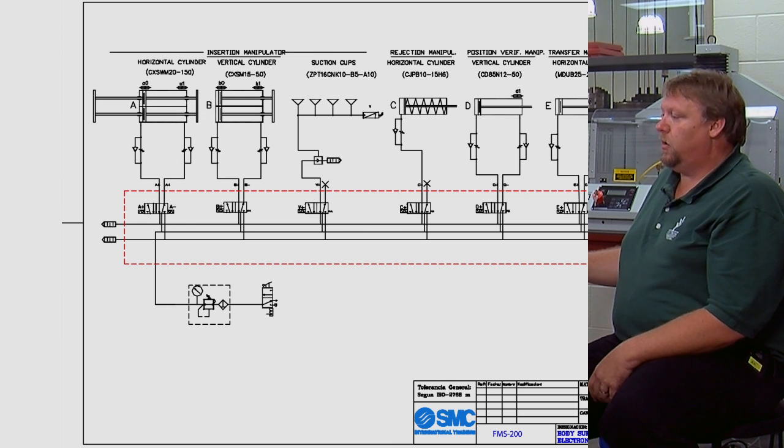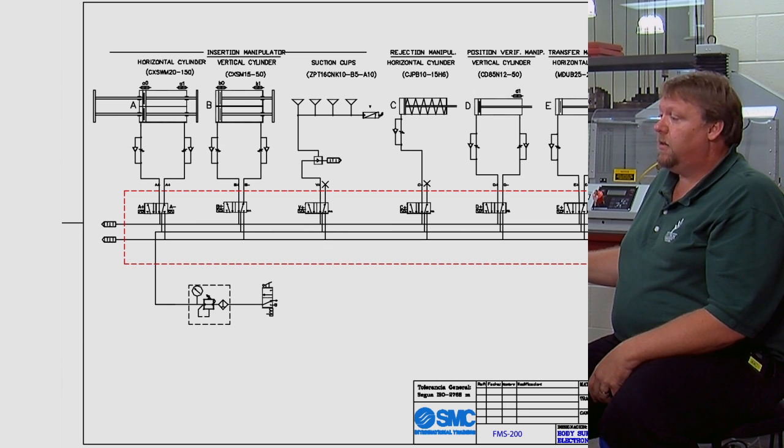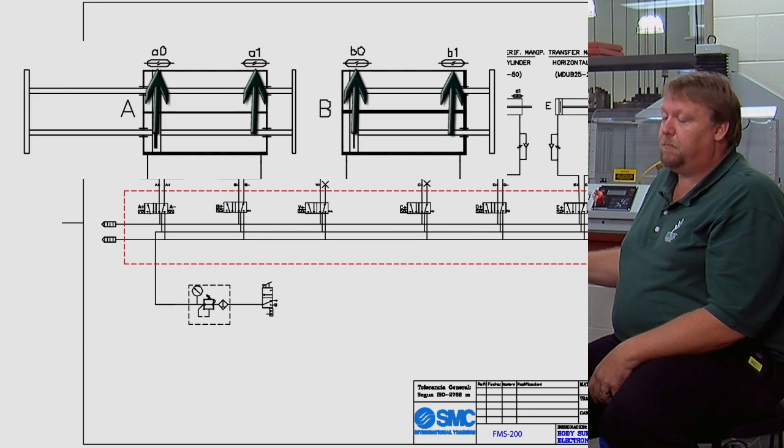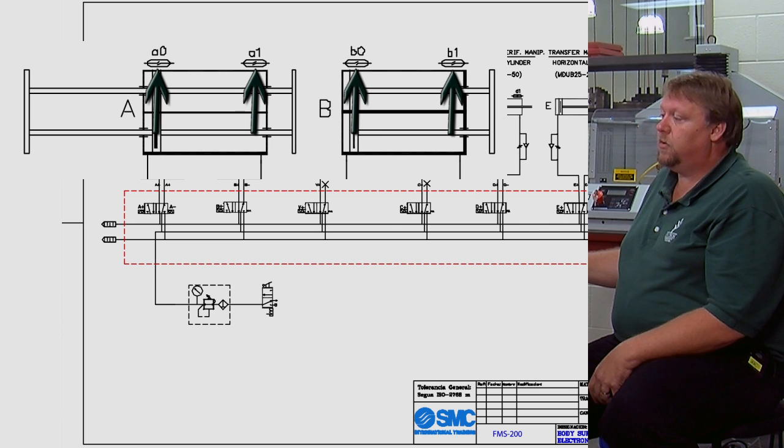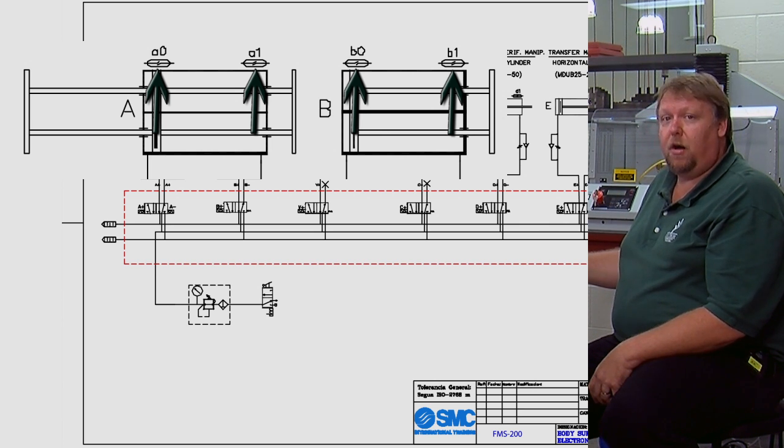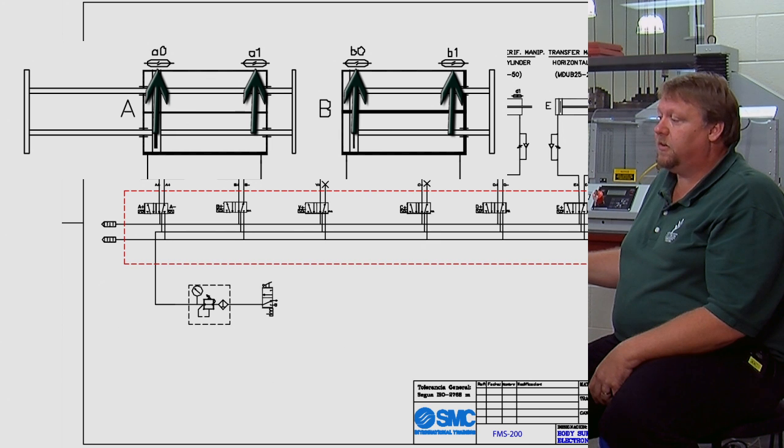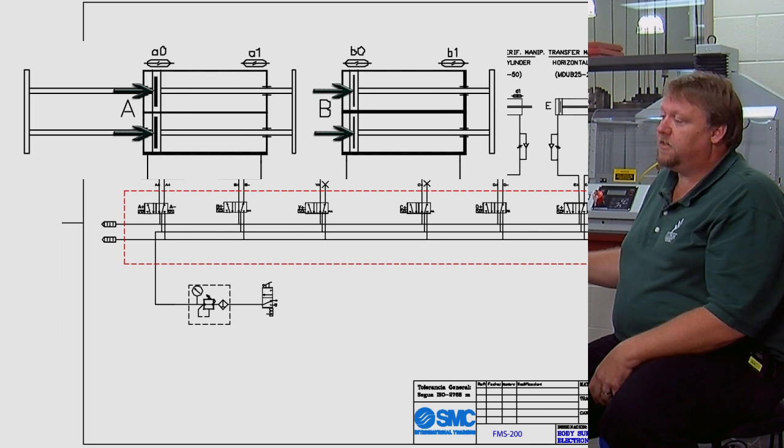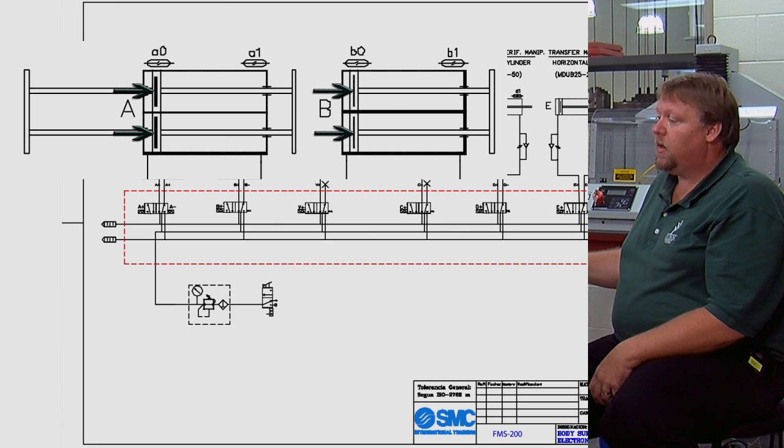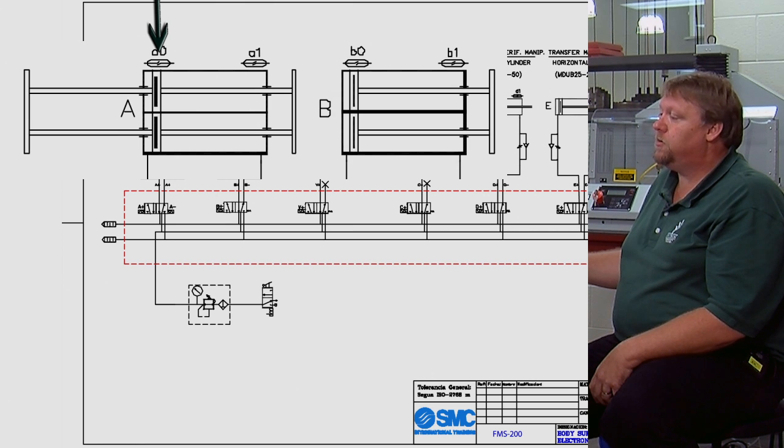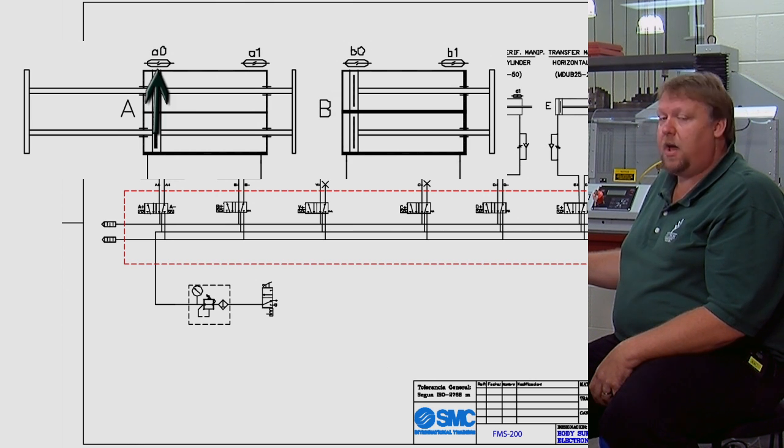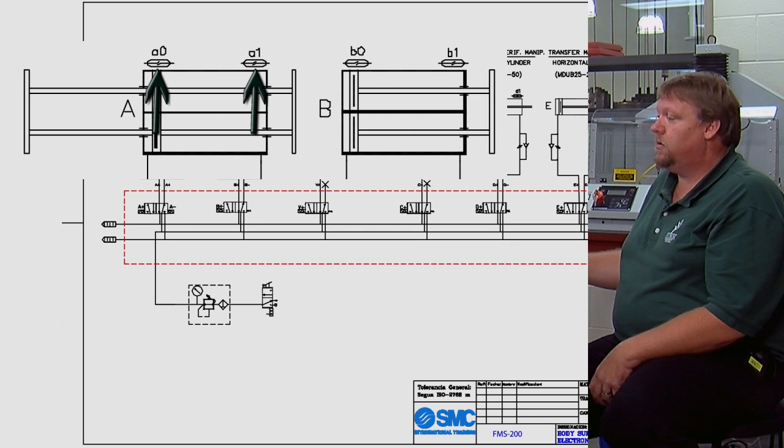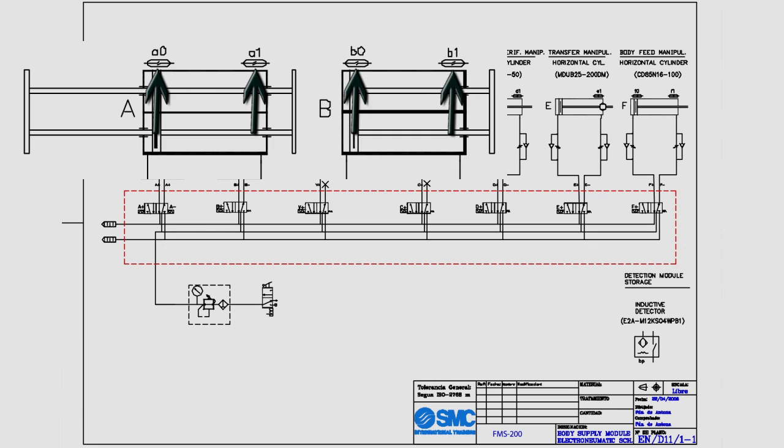Okay the next thing that's really important about both of these cylinders is if we look at the actual top here, this is a magnetic reed switch. So it tells us that each one of these is going to be activated by a magnet and it also allows us to know positioning of the cylinder. So here the magnet is inside here on the piston, it would trigger this switch which is then going to trigger our input that we've seen on the previous page. So here on the horizontal cylinder we have extend and we have retract. On our vertical cylinder we have the same, we have extend and we have retract.